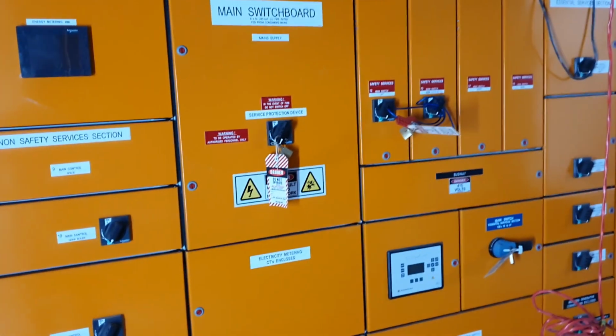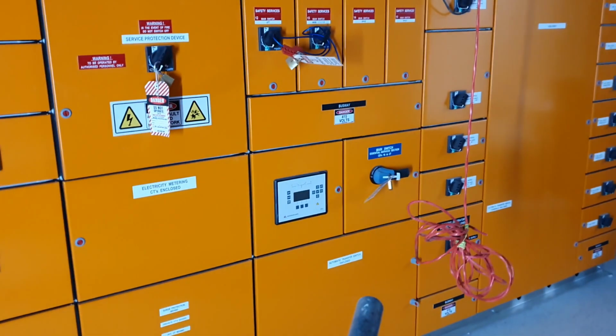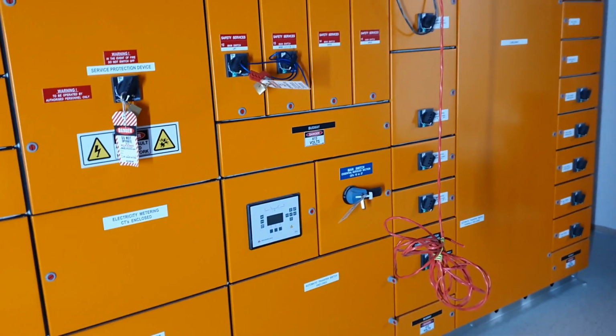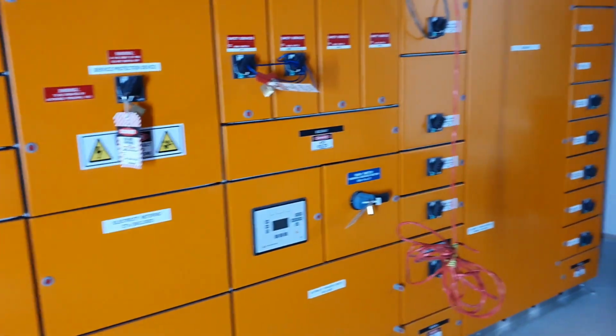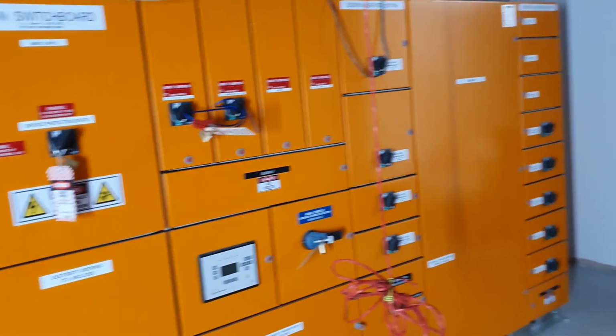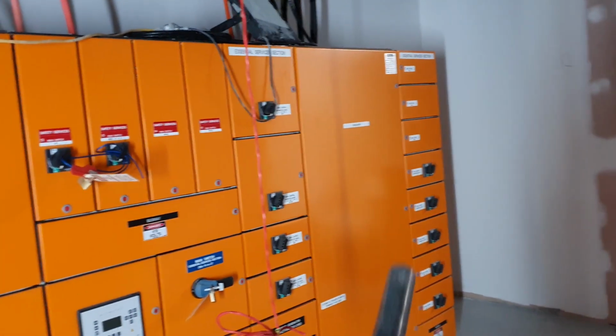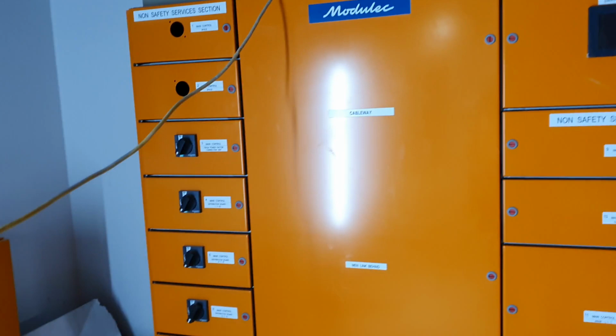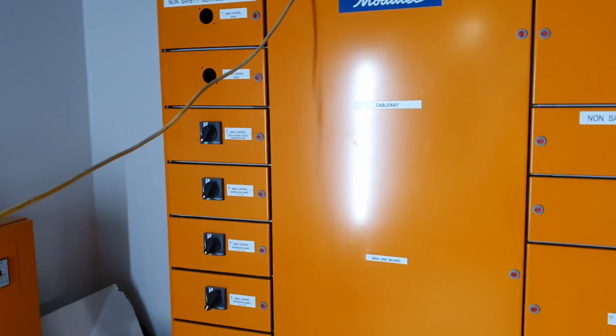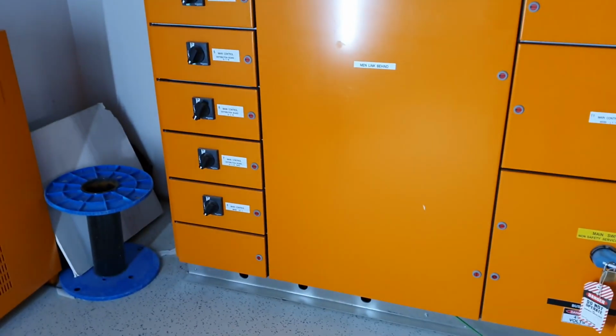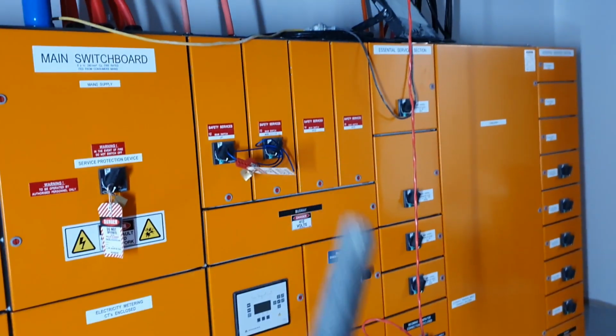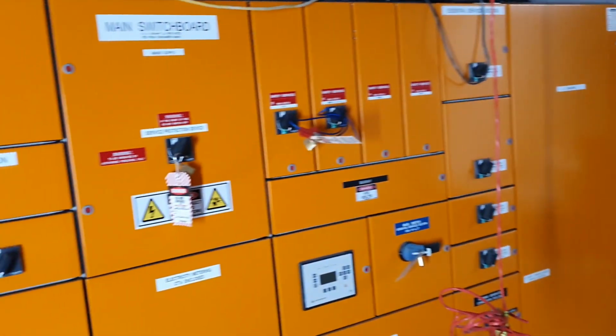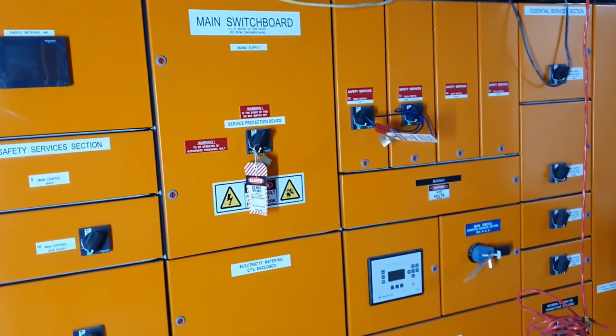Once we get the power on, the process will be to lock every single breaker off. We can turn on the individual parts of the bus bars, each side of it, and I'll keep a lock on every board until I've given it the okay, done all the appropriate tests, and checked everything before we start turning boards on. From there it's the same process - every single circuit gets locked off until it's tested and ready to power up.